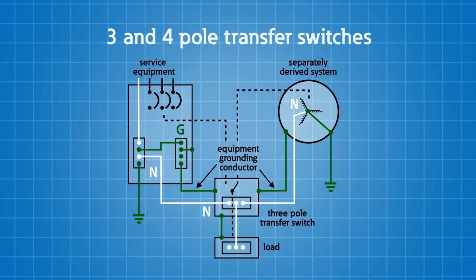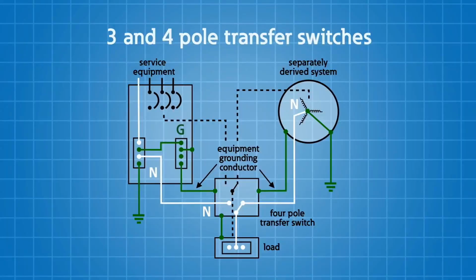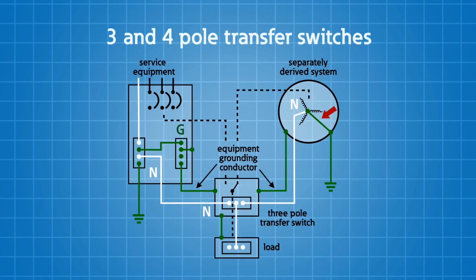A separately derived system implies that you would have a grounding electrode system and you would bond the neutral, the grounded conductor, in the generator with that system. If you have a separately derived system, the implication is that the transfer switch must switch the neutral with a 4-pole transfer switch. But what if I accidentally bonded the neutral to the ground in the generator and I only have a 3-pole transfer switch? How do I fix it? Do I have to buy a 4-pole transfer switch? Sure, you could. Or you could simply unbond the neutral in the generator.